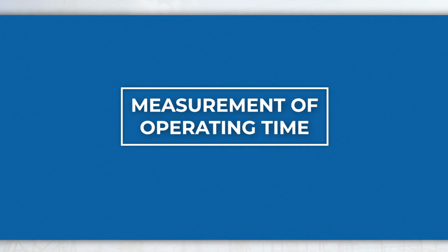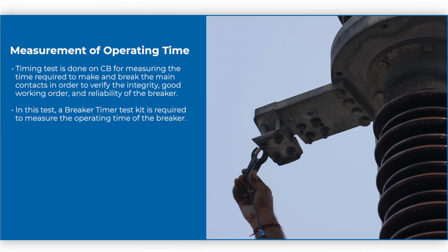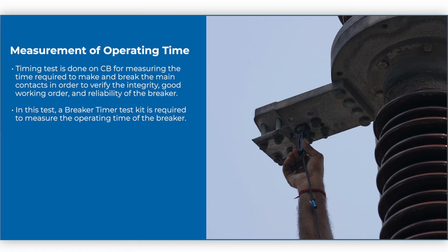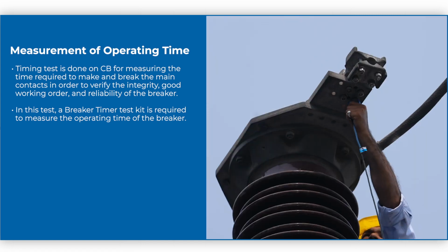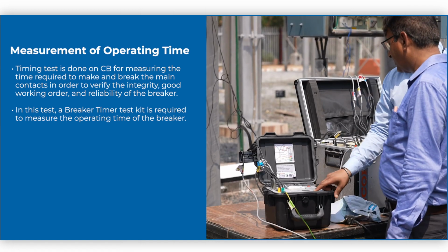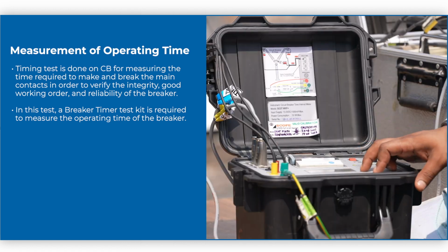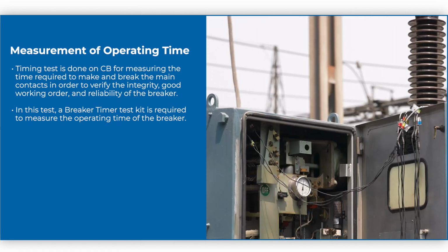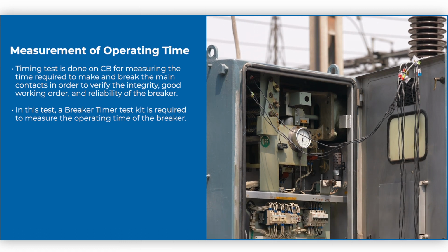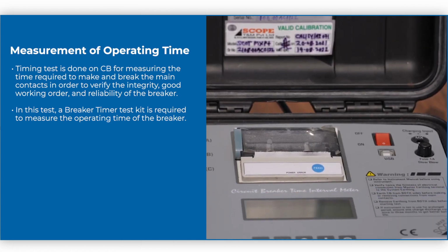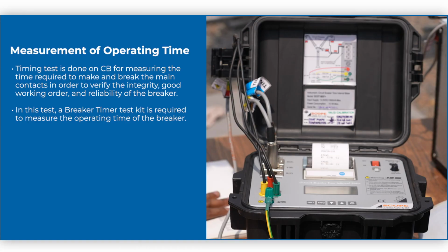Measurement of operating time. Timing test is done on CB for measuring the time required to make and break the main contacts in order to verify the integrity, good working order, and reliability of the breaker. In this test, a breaker timer test kit is required to measure the operating time of the breaker.